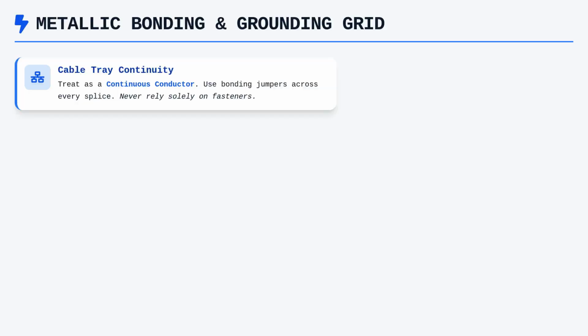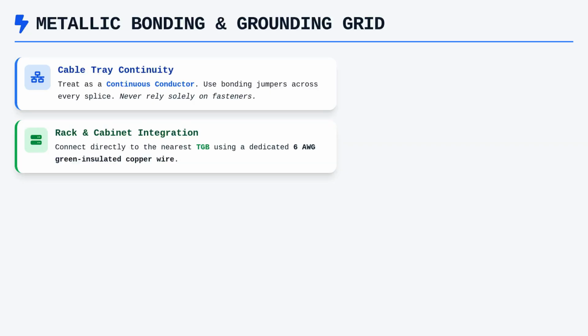As we integrate the various metallic elements of the room into this grid, we must consider the bonding of equipment racks, cable trays, and building steel. You should treat every metallic section of a cable tray system as a continuous conductor by using bonding jumpers across every splice, ensuring that no mechanical joint relies solely on fasteners for electrical continuity. The grounding wire from a rack or cabinet connects directly to the nearest TGB using a dedicated bonding conductor, typically a 6 AWG green insulated copper wire.